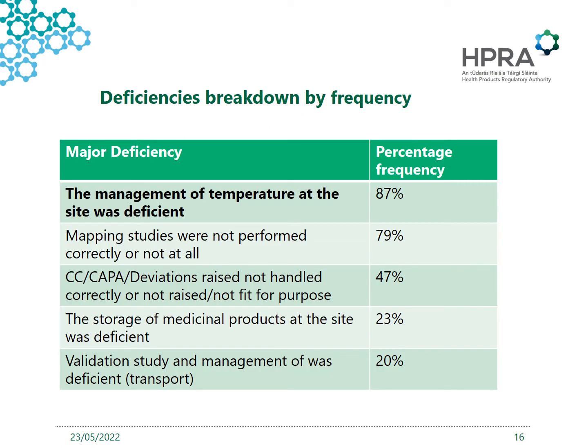Revisiting common deficiencies: we've seen examples where the management of temperature at the site was deficient, including that seasonal mappings were not performed, or that the company failed to document things like the set point, the alarm limits, the use of equipment, or the location of the permanent temperature monitoring probe and the map within the company's QMS.